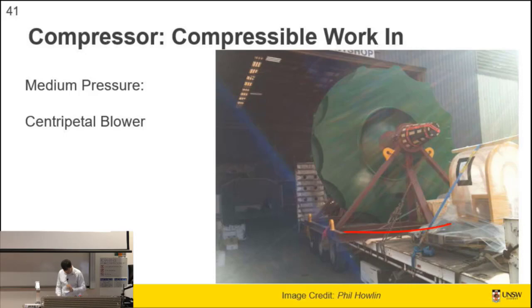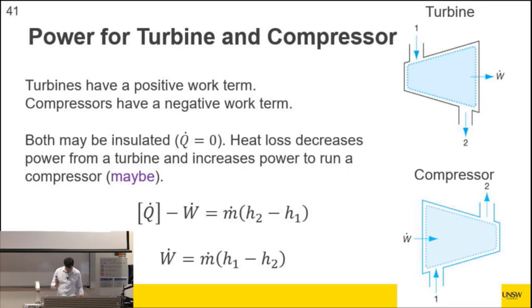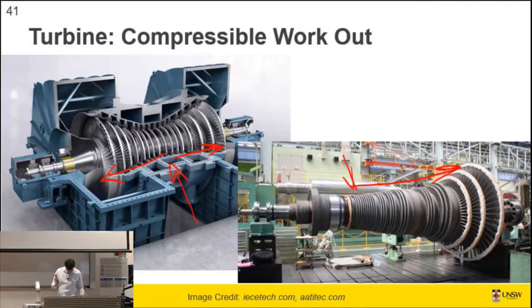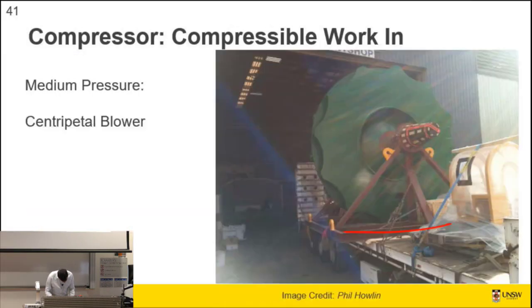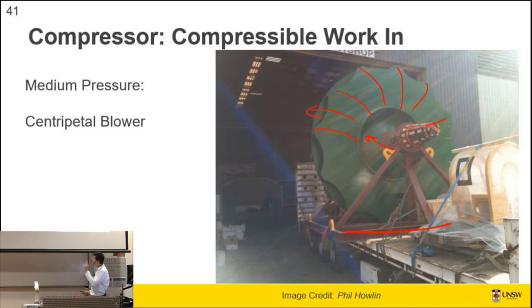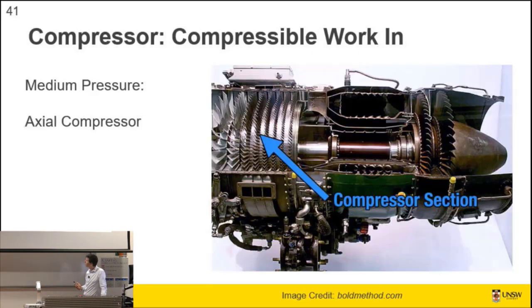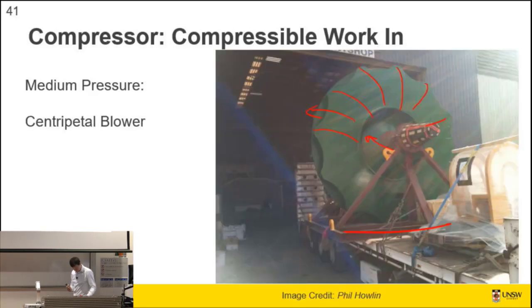This impeller — for a different fan — is about the size of a flatbed truck, around 13 tonnes and worth about $300,000. The vanes are visible; you can see the inlet and outlet. I'll show the housing it sits in later. Centripetal blowers are appropriate for medium pressures and large volumetric flow rates — this particular fan maintains about 13 kPa pressure difference.